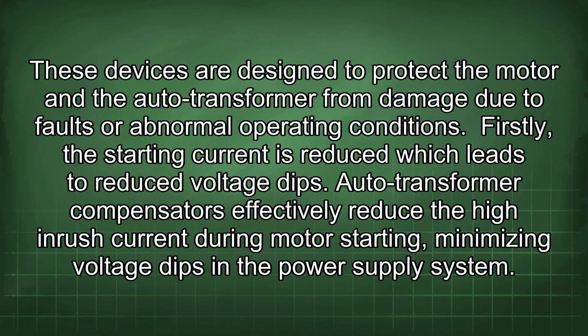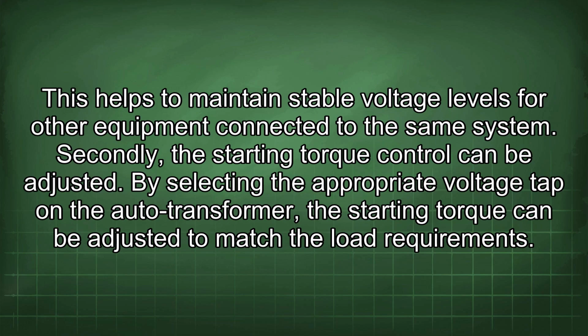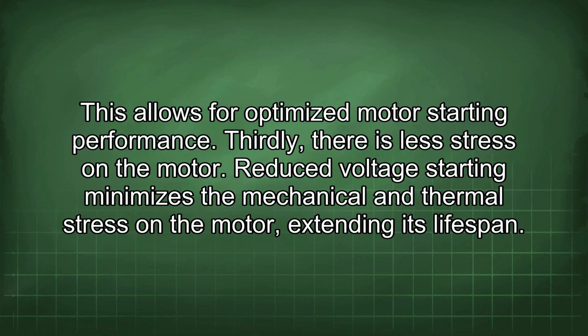Firstly, the starting current is reduced, which leads to reduced voltage dips. Auto-transformer compensators effectively reduce the high inrush current during motor starting, minimizing voltage dips in the power supply system. This helps to maintain stable voltage levels for other equipment connected to the same system. Secondly, the starting torque control can be adjusted. By selecting the appropriate voltage tap on the auto-transformer, the starting torque can be adjusted to match the load requirements. This allows for optimized motor starting performance. Thirdly, there is less stress on the motor. Reduced voltage starting minimizes the mechanical and thermal stress on the motor, extending its lifespan.